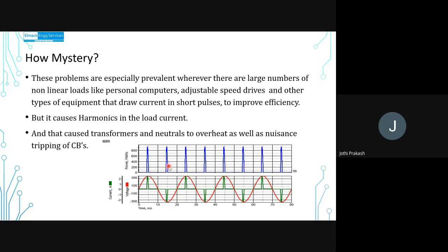This was introduced for a good purpose, to improve efficiency, but in reverse it causes harmonics in the load current. These harmonics in the load current caused the transformers, as we saw in the earlier pictures, and the neutral conductors to overheat as well as burn out. And this is also a major cause of tripping of circuit breakers.